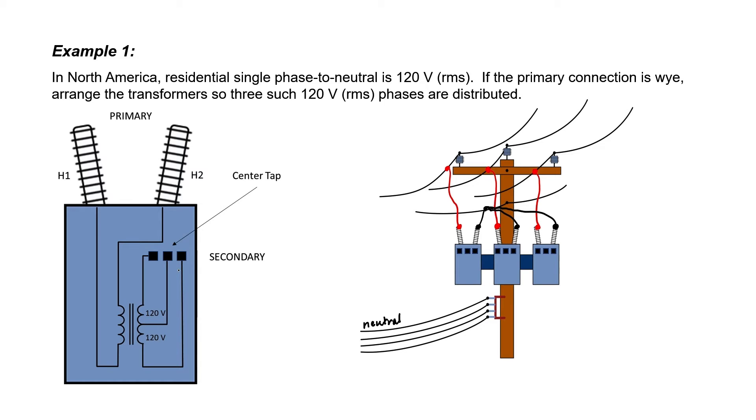If we look over here at our diagram for the transformer, we can see that we have 240 volts across the secondaries of this transformer, and we have 120 volts RMS between the center tap and either of the other two secondaries.